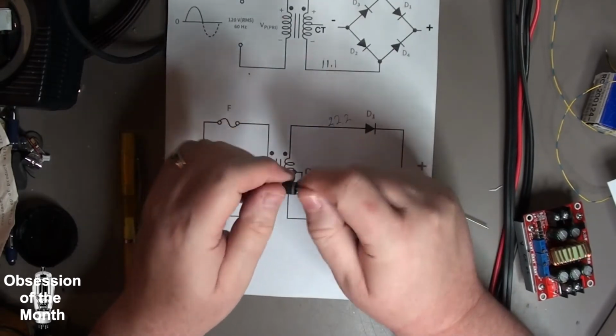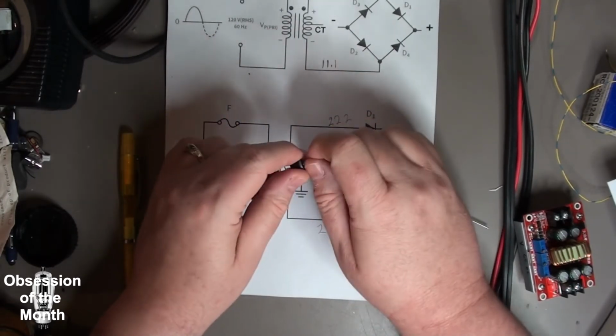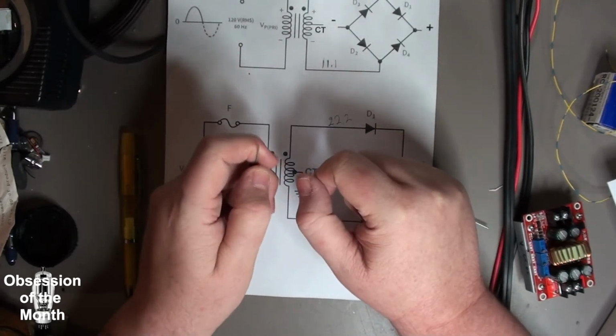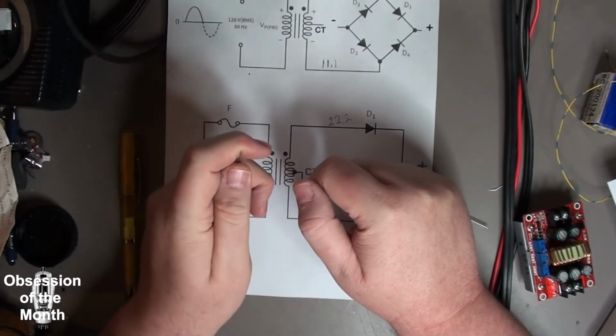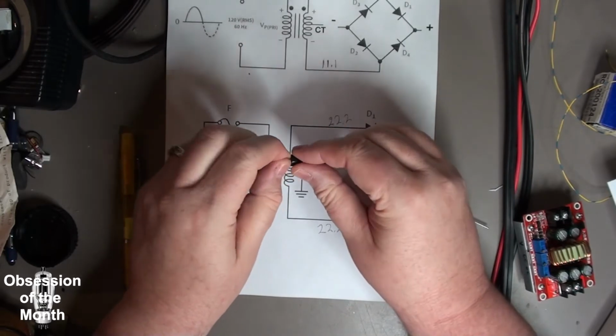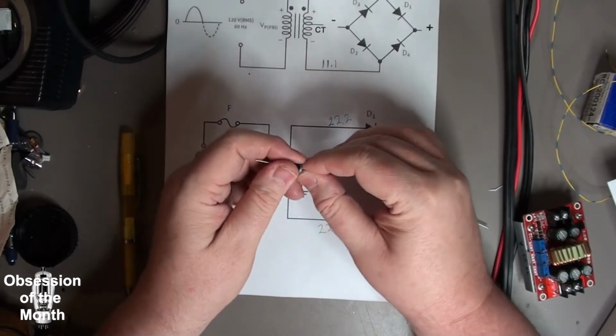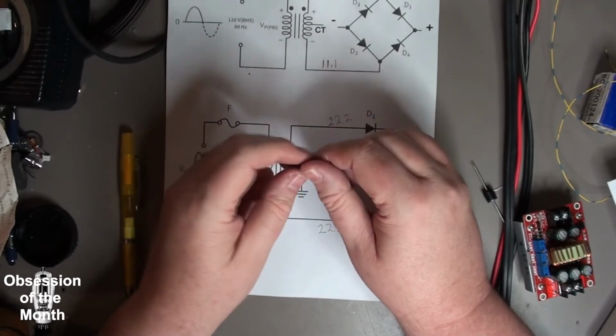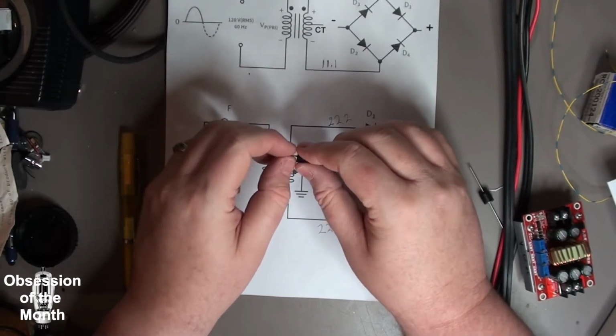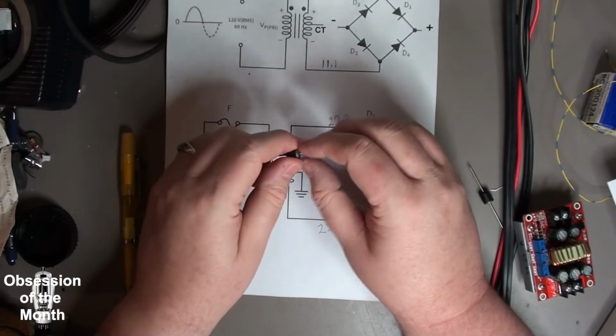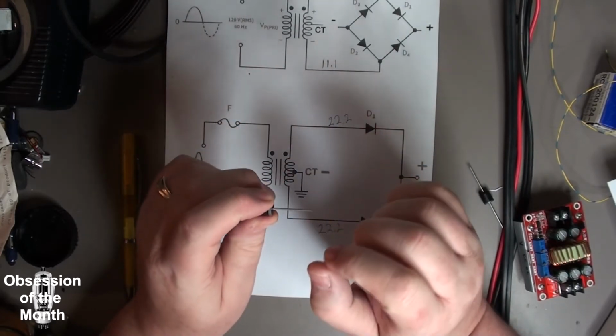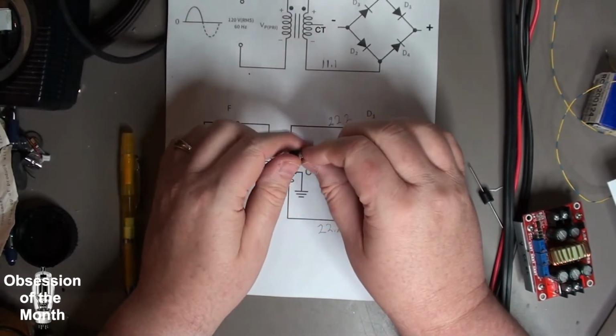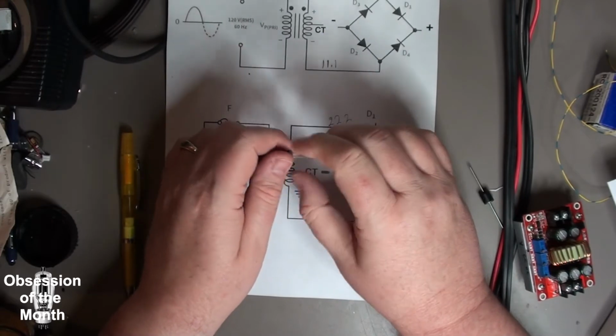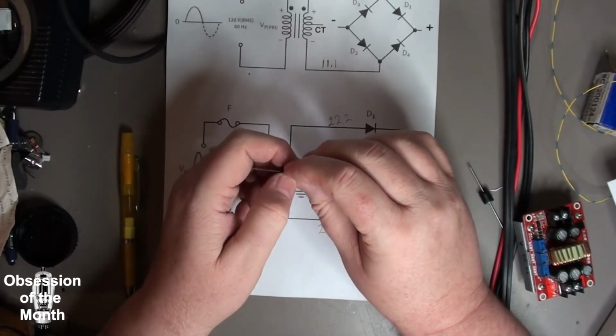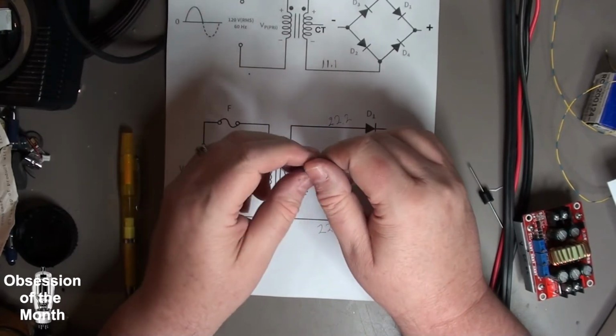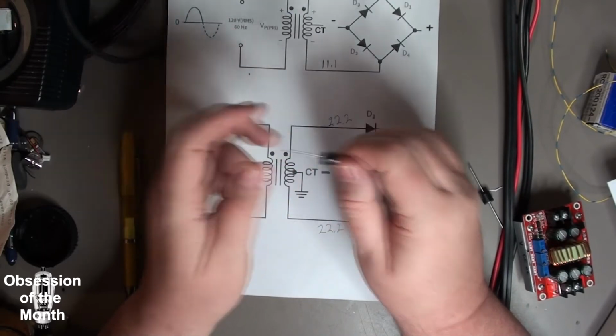If your charger puts out 8 amps, it doesn't mean it's going to shove 8 amps into the battery, but it does mean the battery can draw more current than it should, and a battery will draw what it wants. So if it wants to draw 4 or 5 amps, it'll do that, but it may not be good for the battery - that's why you need current limiting. Most automotive dumb chargers are usually in the 6 to 10 amp range, and most car batteries and deep cycle batteries are fine being charged between 6 and 10 amps. It won't hurt them - it's usually within their rated charging capacity.